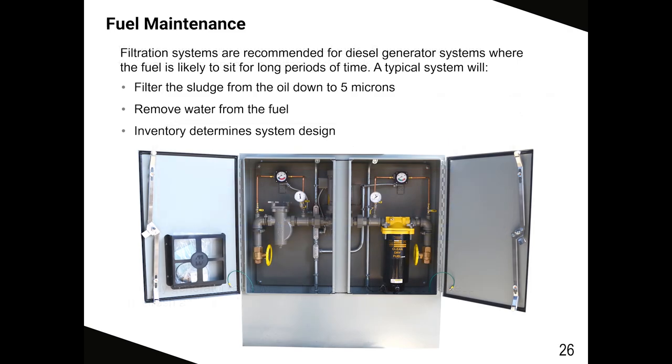This is a typical fuel oil maintenance system. These are standard designs capable of filtering up to 20,000 gallon tanks. A typical system will filter the sludge from oil down to 5 microns, remove water from the fuel, and include a self-contained leak detection and alarm.